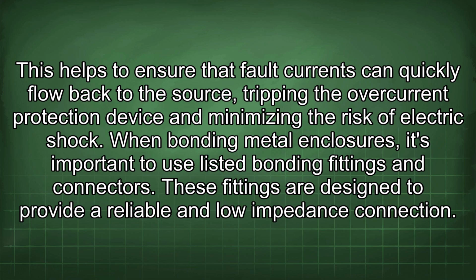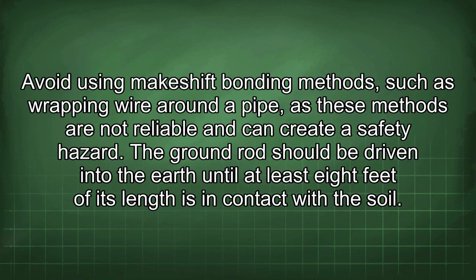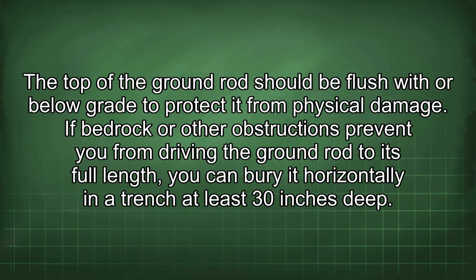When bonding metal enclosures, it's important to use listed bonding fittings and connectors. These fittings are designed to provide a reliable and low impedance connection. Avoid using makeshift bonding methods such as wrapping wire around a pipe, as these methods are not reliable and can create a safety hazard. The ground rod should be driven into the earth until at least 8 feet of its length is in contact with the soil. The top of the ground rod should be flush with or below grade to protect it from physical damage.